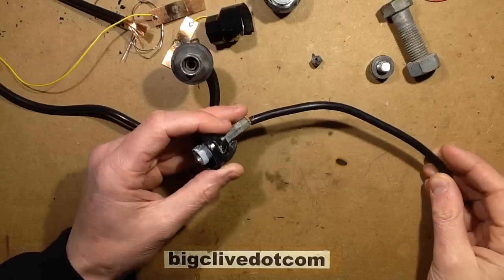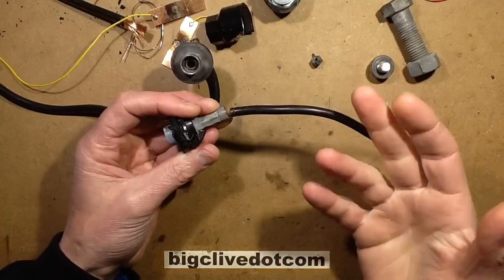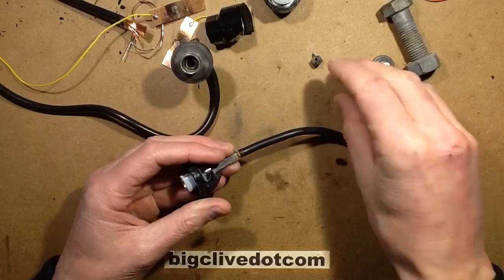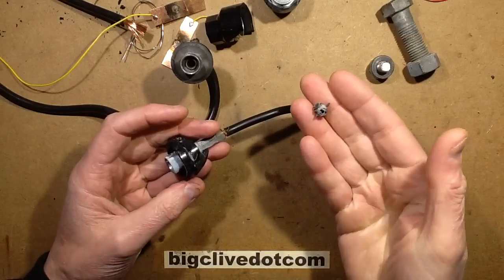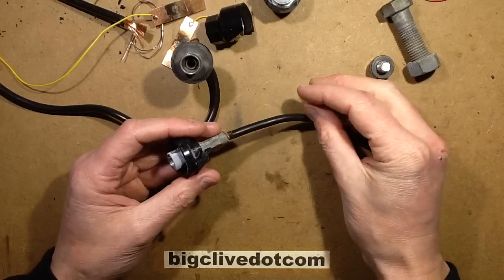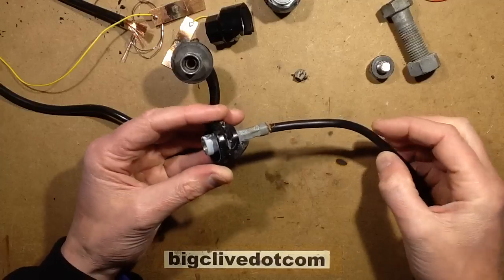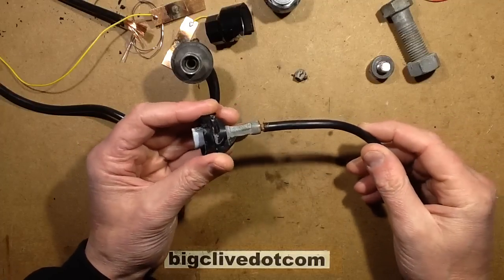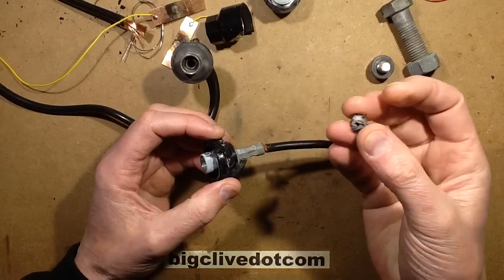A little update video for the explosive disconnector video that I couldn't work out why it was so loud. It seemed really unusually loud for something like this, just blowing that apart with pressure alone. And in the comments, Zlobodan from Sweden mentioned that their explosive disconnectors have a shell in them — a small explosive charge — and the carbon pin is just for heating it.